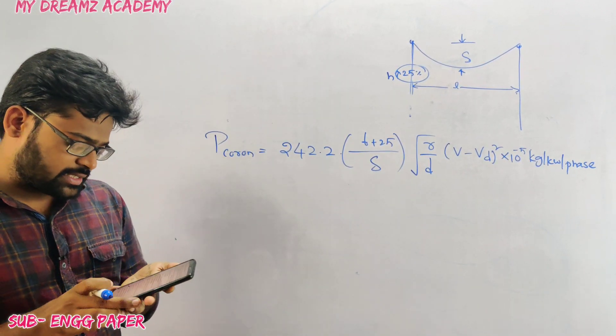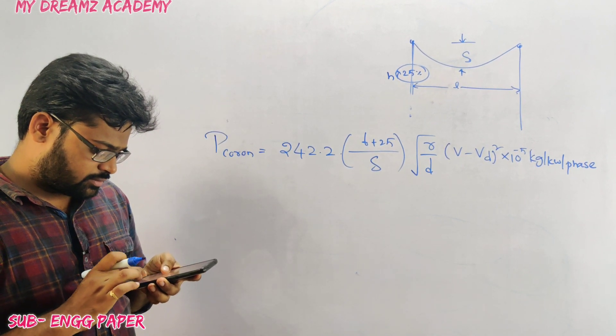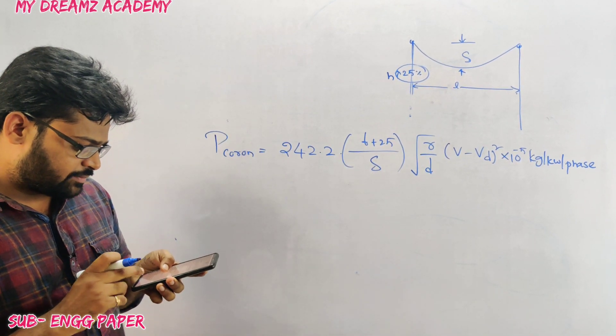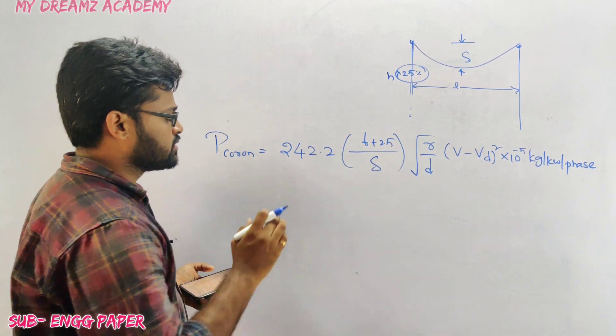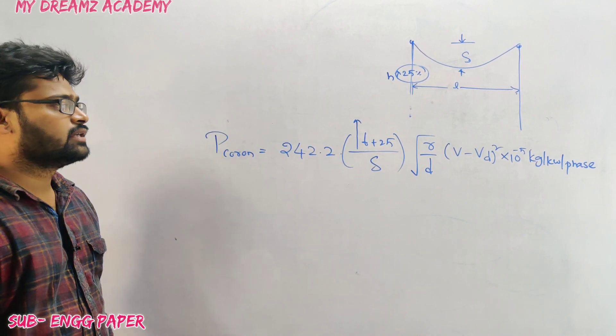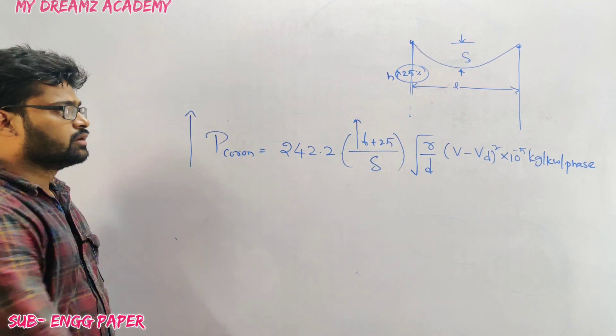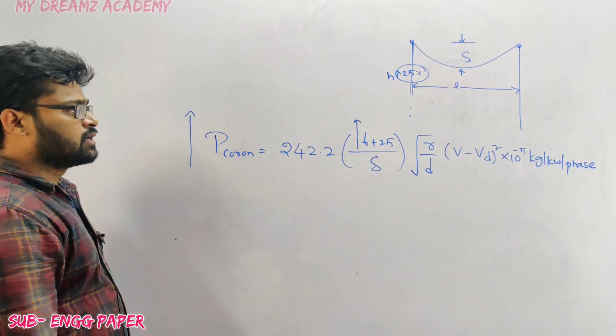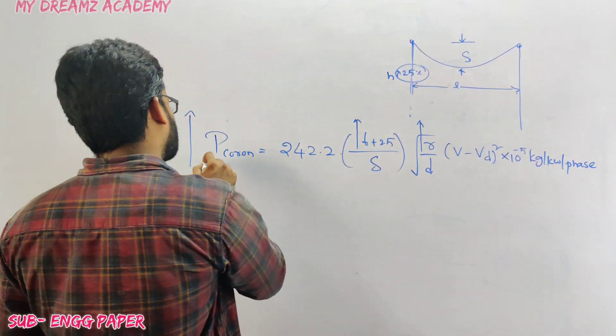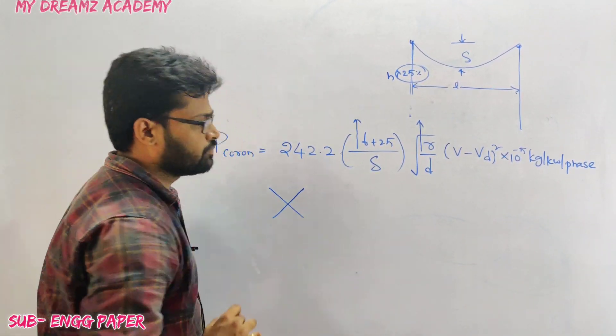Corona loss increases with decrease in conductor size and increase in frequency. If frequency increases, corona loss increases. If the radius of the conductor increases, it might seem corona increases since the formula has r directly, but this is a wrong perception.